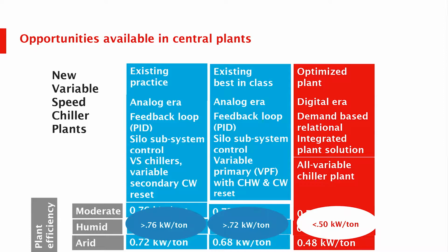But typically, with best-in-class, or at least good practice now, people still use a PID loop, and the systems are still relatively siloed—they don't communicate well and don't really integrate from an operational perspective. So even if they have variable speed chillers and reset, a lot of things people do now, you're probably still got a system somewhere in the 0.75, 0.76 range for the aggregate plant. There's been a movement toward a bit more integration, still PID, and still a fair degree of isolation or controlled variance between pumping and the cooling towers.